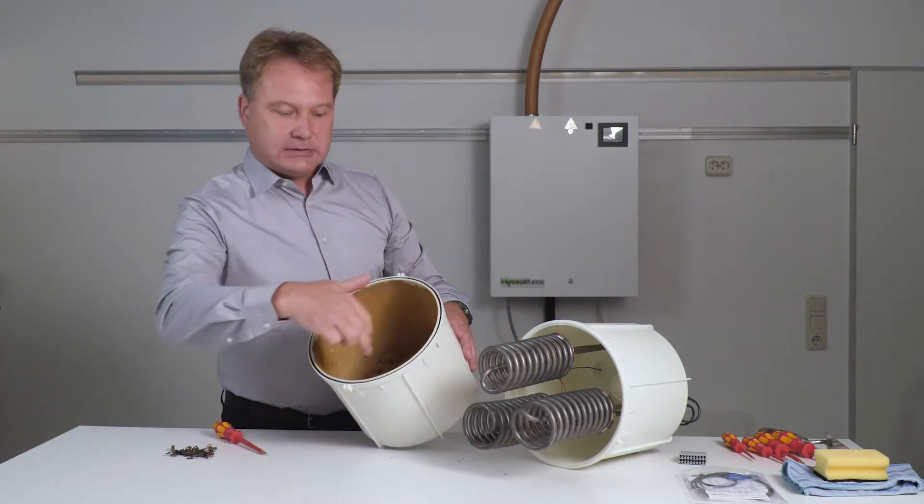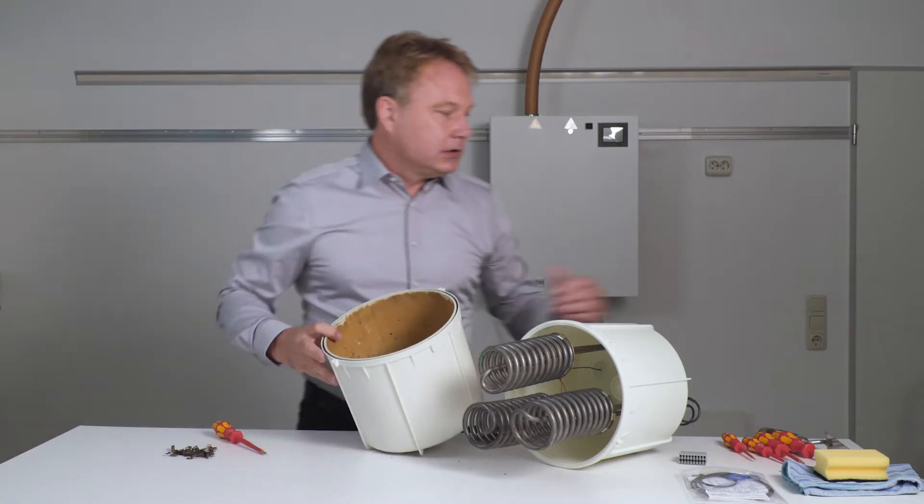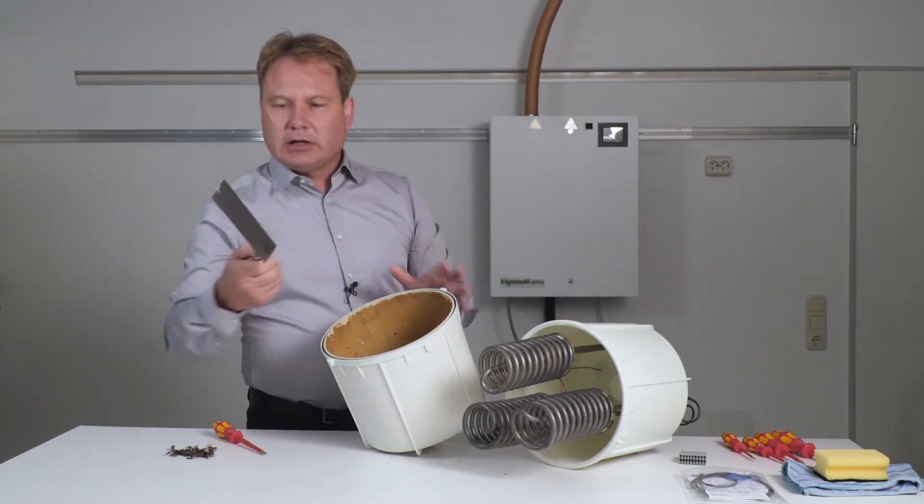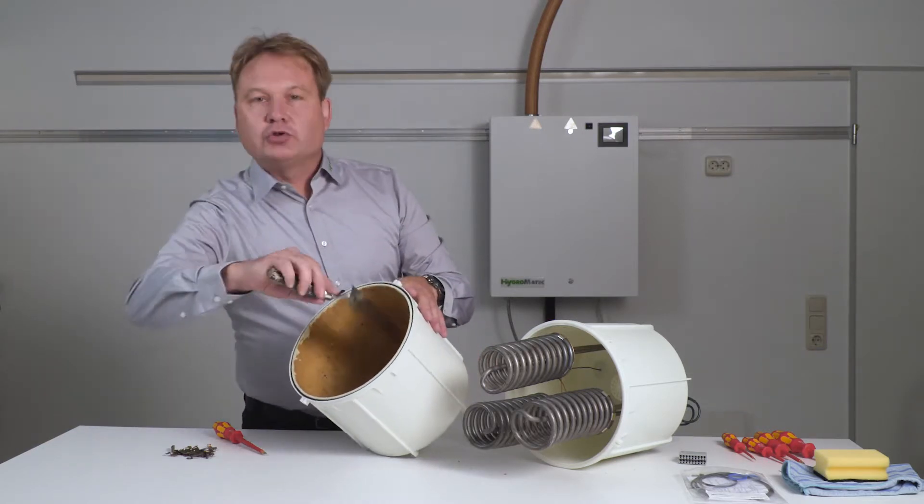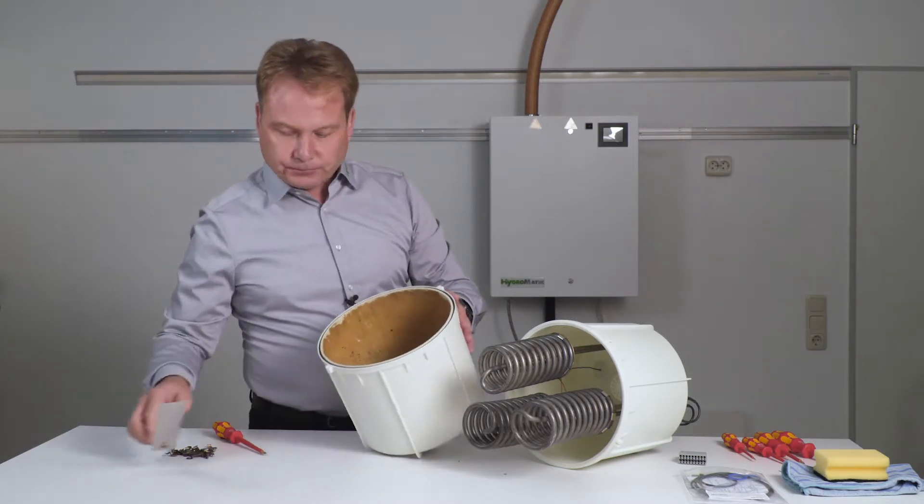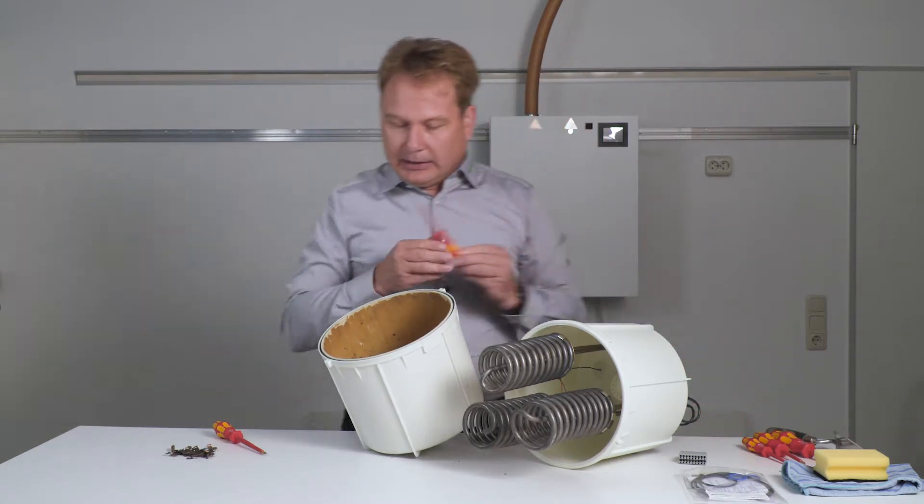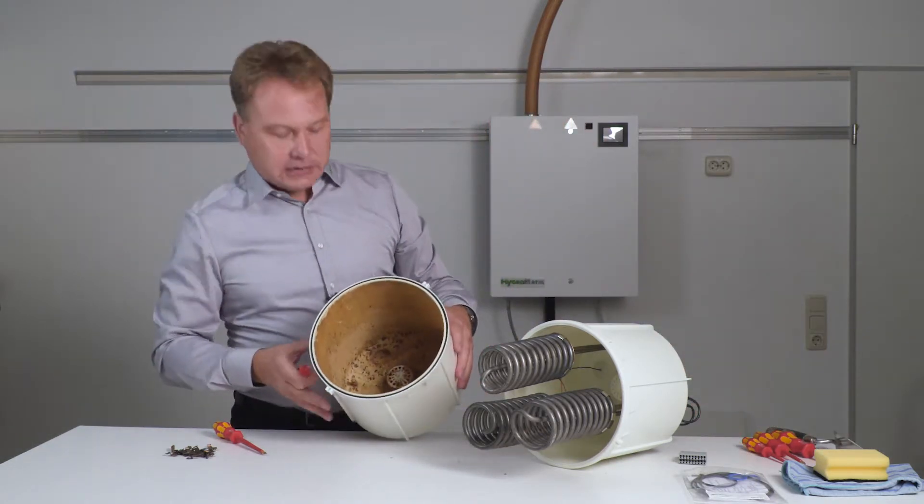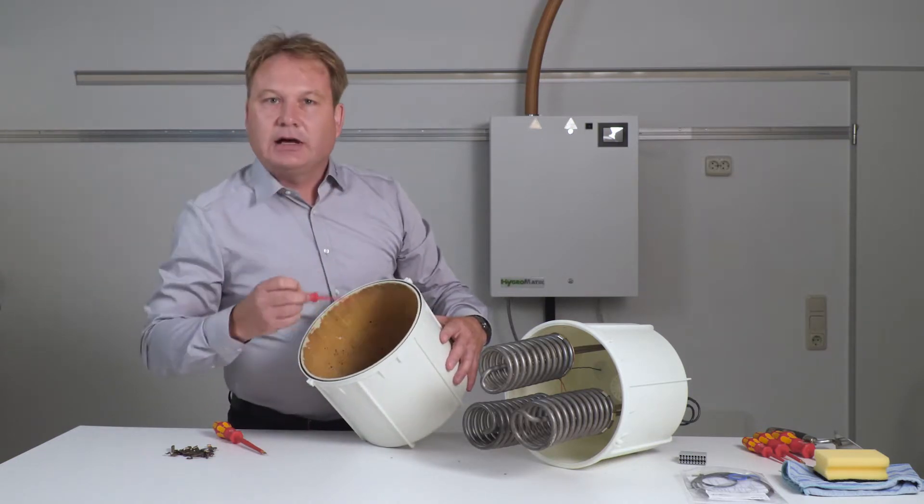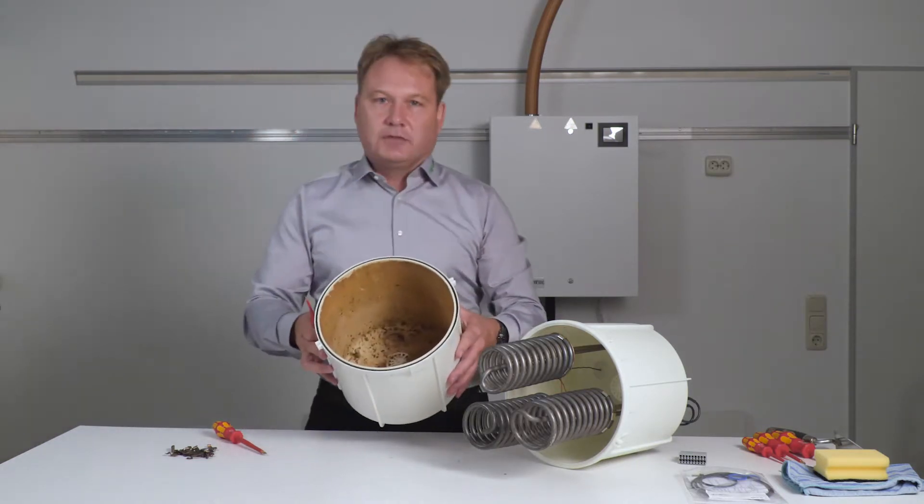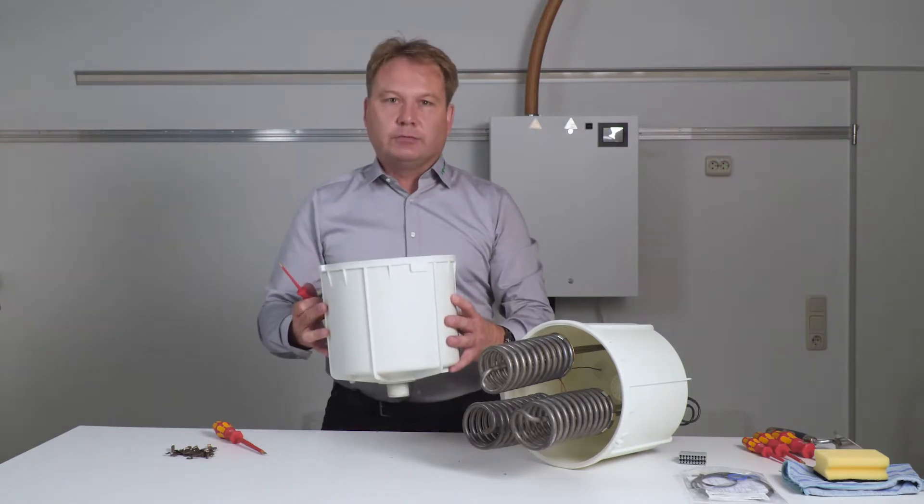To remove the coarse particles from the cylinder wall, you can use a standard scraper or spatula and remove the coarse particles. Please also clean the cylinder strainer that we see here. The holes, of course, must be clear so the cylinder water can be pumped out completely.